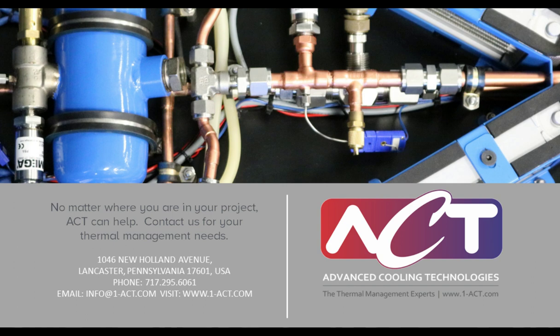As we mentioned during the presentation, liquid cooling systems often require faster flow rates in order to achieve the same performance as a pumped two-phase system. Higher flow rates and higher pressure drops translate to more power required to drive the fluid around the loop. In a pumped two-phase system, the energy capacity and the latent heat of vaporization of the fluid is 2 to 4 times greater than the sensible energy that can be absorbed in the single-phase cooling system, and therefore it requires less mass flow rate to dissipate the same amount of power. Less mass flow rate and lower pressure drops equal less pumping power, which means less energy needs to be supplied to the system for a pumped two-phase system as compared to a single-phase system.